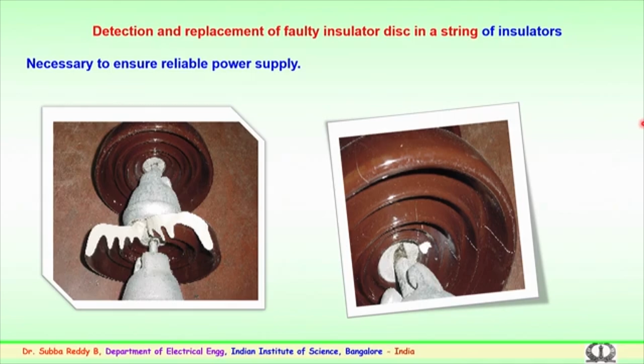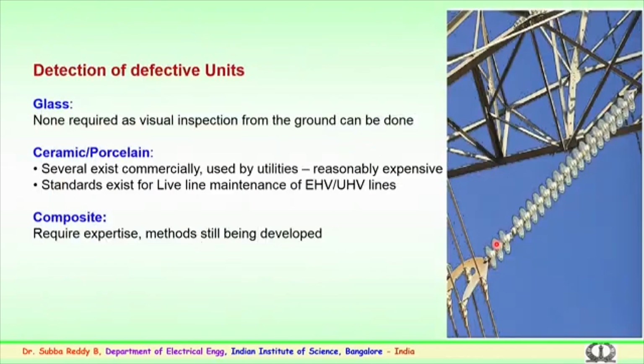These faulty insulators could be due to several reasons. It could be because of vandalism, it could be because of overvoltages which could have shattered the sheds, or it could be because of the Portland cement near the pin junction, wherein the cement growth happens over a period of time and the cracking of the insulator happens, and the insulator becomes faulty.